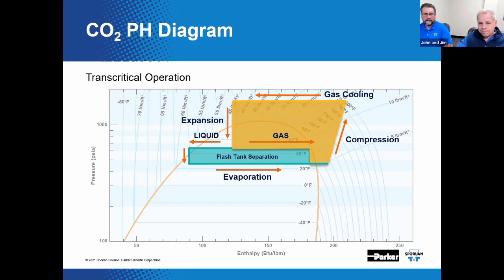It's kind of counterintuitive, but when you do that expansion process of that gas that you've cooled, you actually do create some liquid. If you follow that process dropping into the vapor dome, it becomes apparent that you do. Well, it's flash. So the flash tank separates the liquid and vapor and sends the liquid to the electrically actuated, electronically controlled expansion valves and routes the gas to the medium temp compression stage.